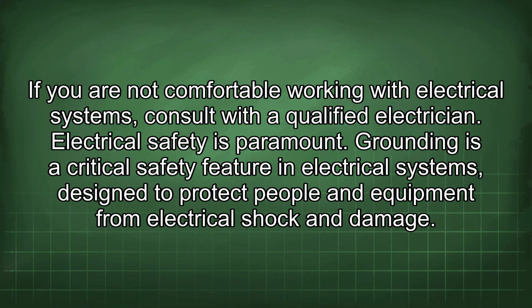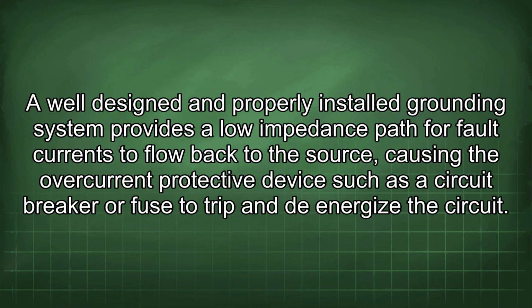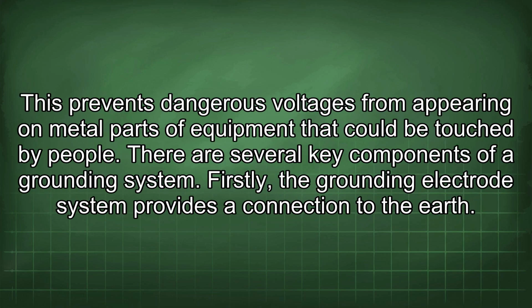electrical shock and damage. A well-designed and properly installed grounding system provides a low impedance path for fault currents to flow back to the source, causing the overcurrent protective device such as a circuit breaker or fuse to trip and de-energize the circuit. This prevents dangerous voltages from appearing on metal parts of equipment that could be touched by people. There are several key components of a grounding system.